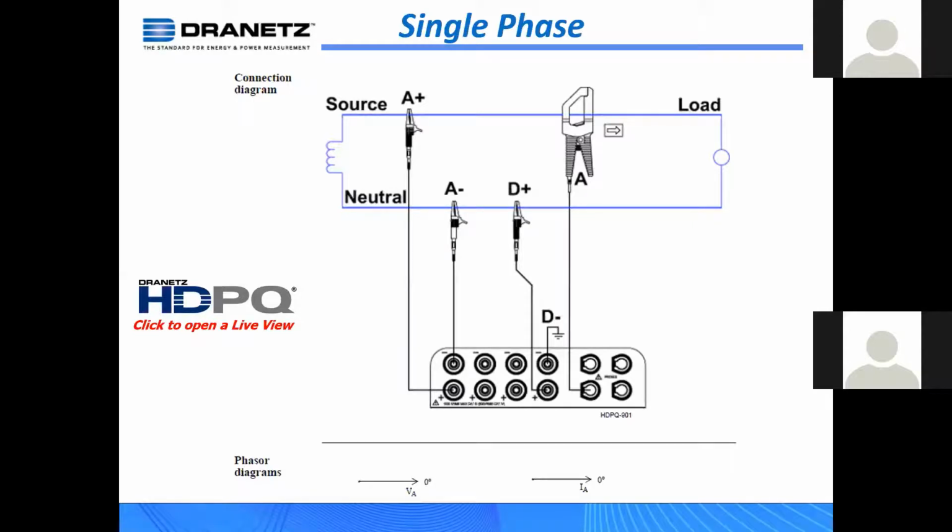You want to make sure this is right, because it's hard to undo this stuff later if you walk away for 30 days and then call Ken or Thurman and say, hey, my data isn't right, what do I do? We can't undo a measurement of the instrument. Our Transducer software can reverse the CT, but any measurements previously made, we can't undo that for you, okay? So spend a couple minutes and make sure it's done right. That's the rule of thumb.